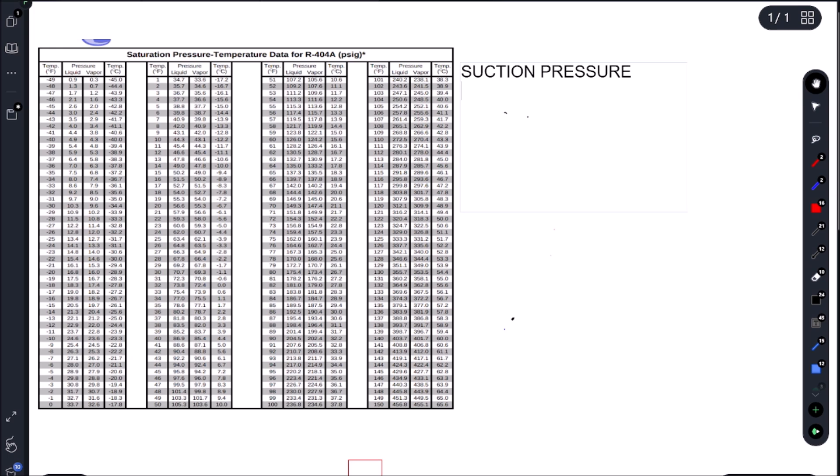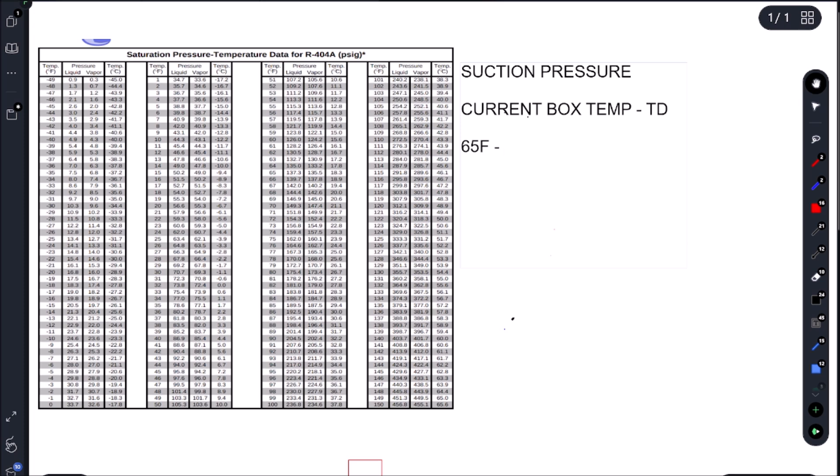Let's go figure out what our suction pressure should be. So this one's a little bit different than the ones we've been working on. It's a TXV reach-in. So how we're going to figure that out is we're going to take our current box temp and we're going to subtract our TD. So in the past with our cap tube, we were using desired box temp. Because we have a TXV, we're going to use current box temp. So our current box temp was 65 Fahrenheit. And our EVAP TD is a 20 TD coil because it is a reach-in. So we're going to subtract 20 Fahrenheit, and that's going to give us 45 Fahrenheit.